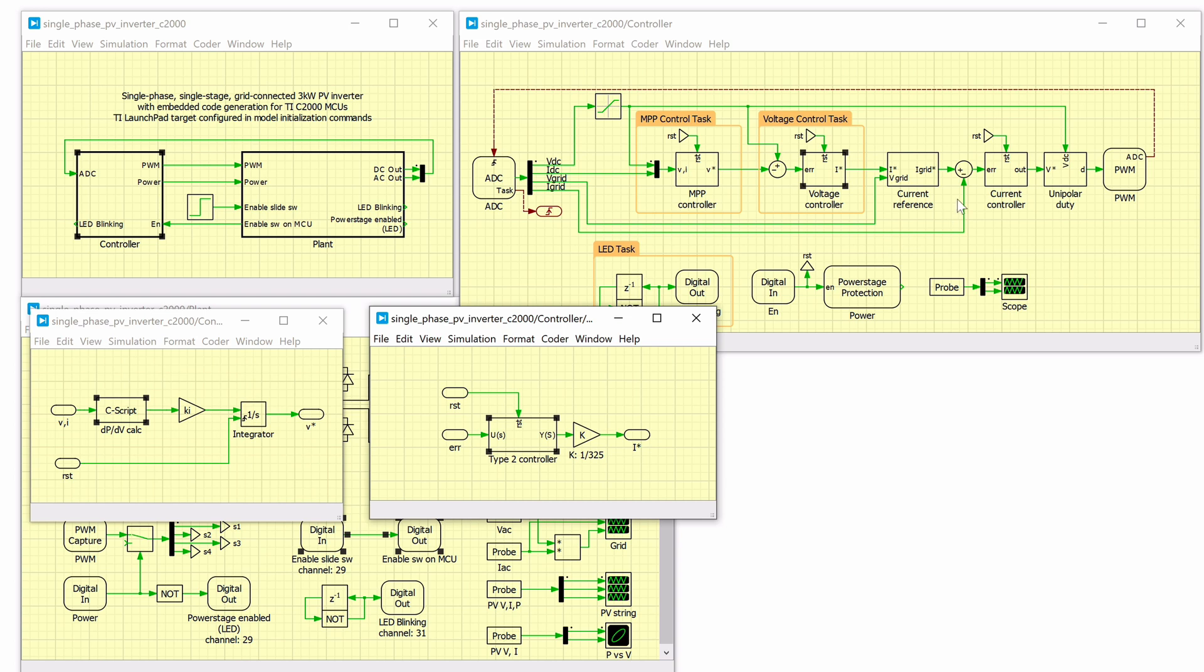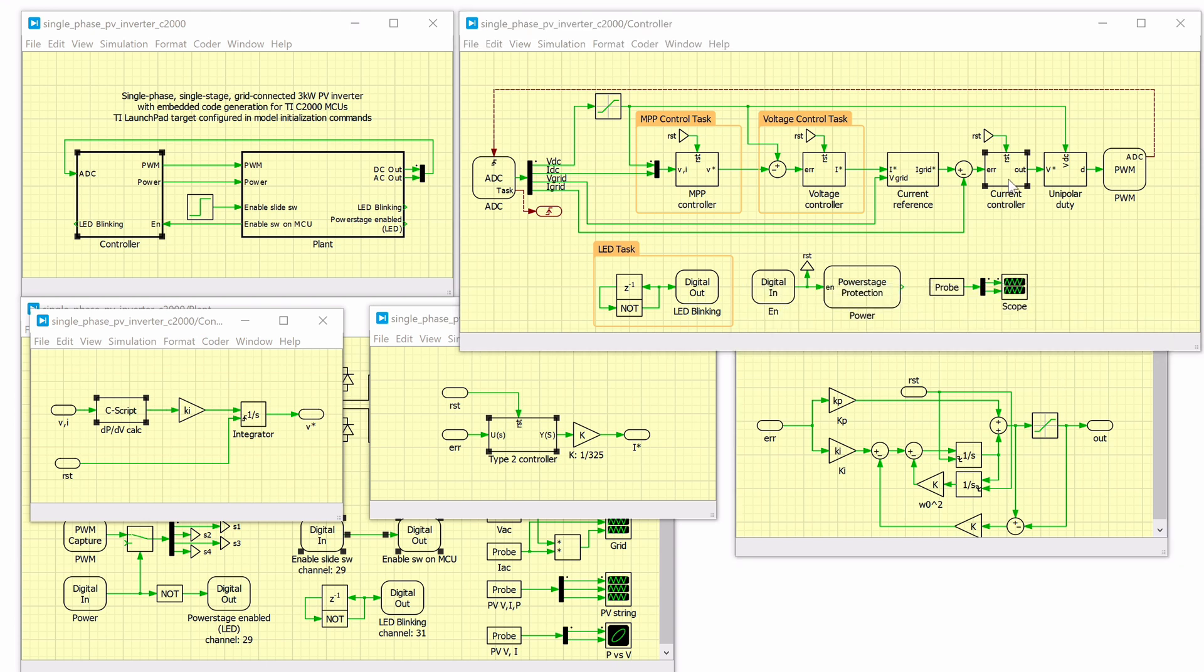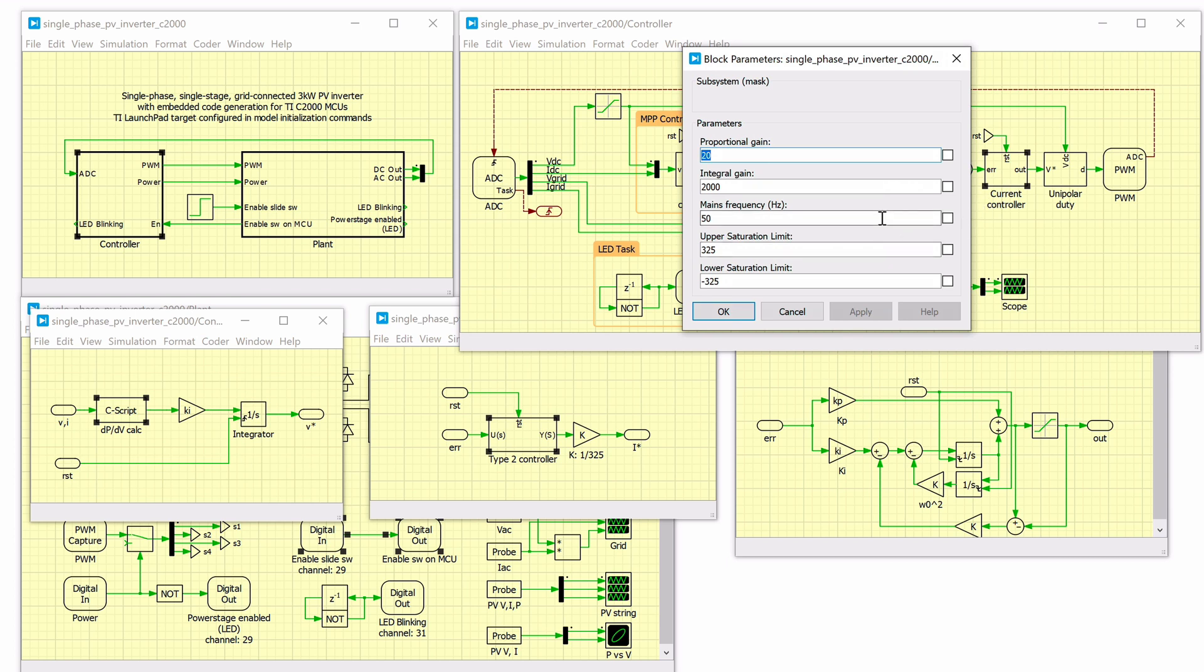The innermost control loop, the current controller, sets the modulation index of the inverter such that the desired current is injected into the grid. The current controller is based on a proportional resonant controller with a resonant frequency of 50Hz to ensure no tracking error is present.